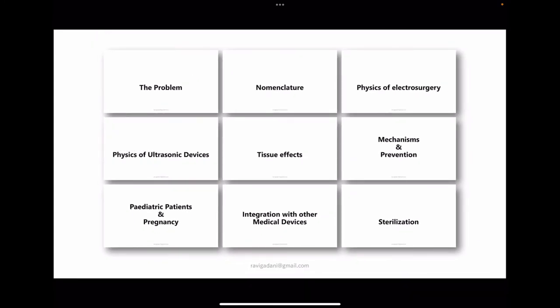To summarize the physics: wall outlet at 50 Hz → electrosurgical unit converts to 500,000 Hz → cations and anions in cells oscillate between poles at that frequency → kinetic energy → friction generates heat → thermal energy. The same mechanism applies to ultrasonic devices, which also create heat. Now let us look at the tissue effects of that heat.